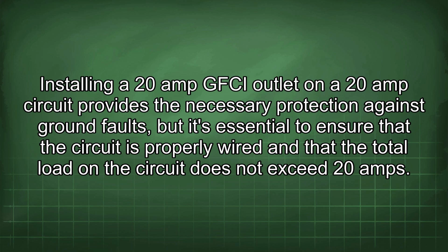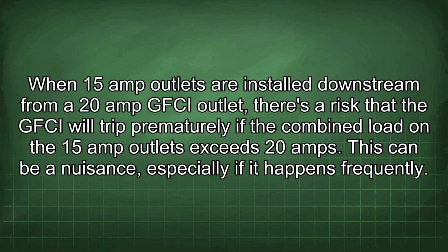Installing a 20 amp GFCI outlet on a 20 amp circuit provides the necessary protection against ground faults, but it's essential to ensure that the circuit is properly wired and that the total load on the circuit does not exceed 20 amps. When 15 amp outlets are installed downstream from a 20 amp GFCI outlet, there's a risk that the GFCI will trip prematurely if the combined load on the 15 amp outlets exceeds 20 amps.